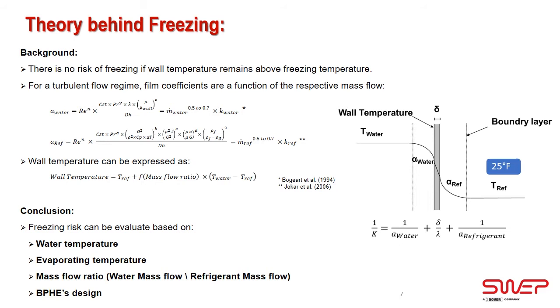Why is the mass flow ratio an important parameter? Let's consider what happens if you change the mass flow ratio. If you increase the mass flow ratio, which means you increase the water flow for a constant refrigerant flow, then the surface temperature or wall temperature will get closer to the water temperature. On the opposite, if you decrease the mass flow ratio, then the surface temperature will move towards the evaporating temperature. So, as a conclusion, in order to evaluate the risk of freezing for a brazed plate heat exchanger, what is important to consider is the water temperature, the evaporating temperature, the mass flow ratio, but also the brazed plate heat exchanger design, as it might change the film coefficient on either side of the heat transfer surface.